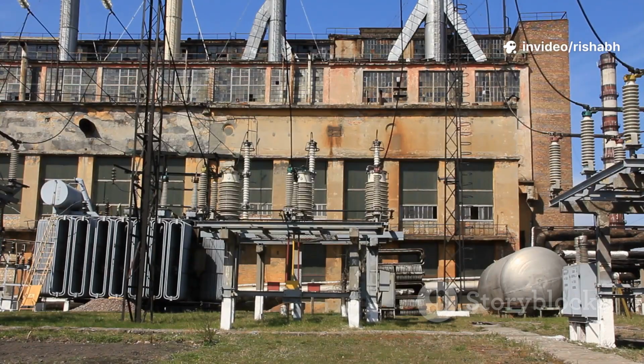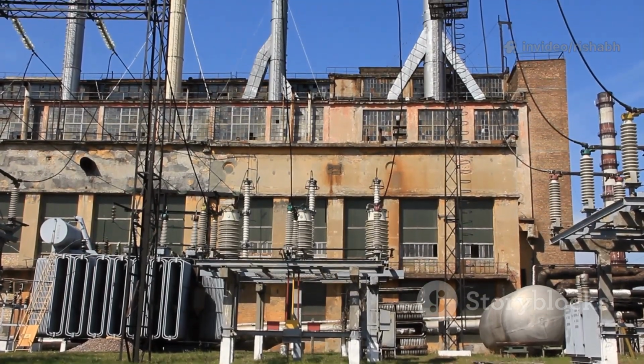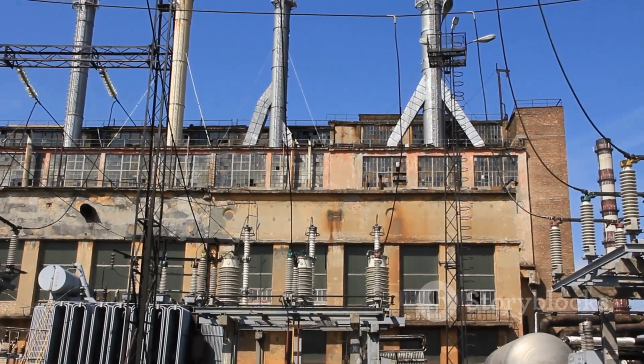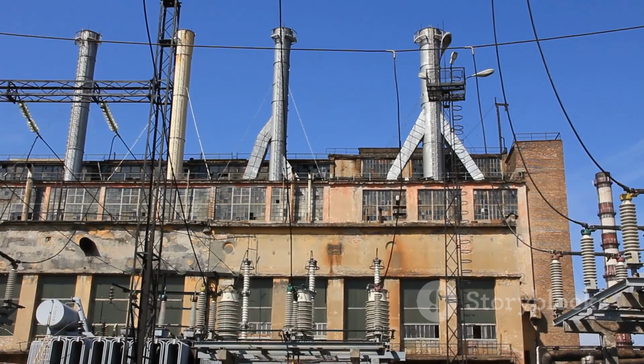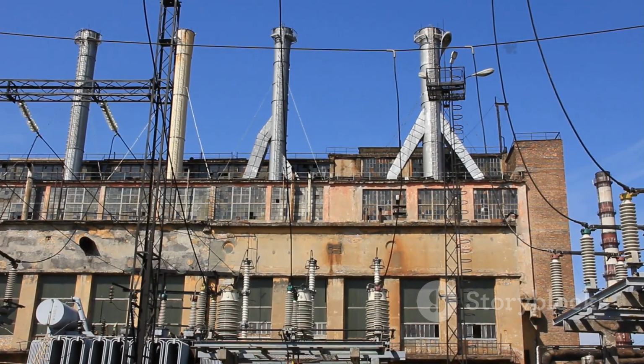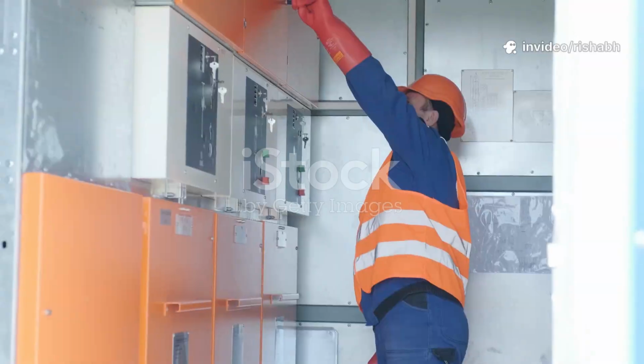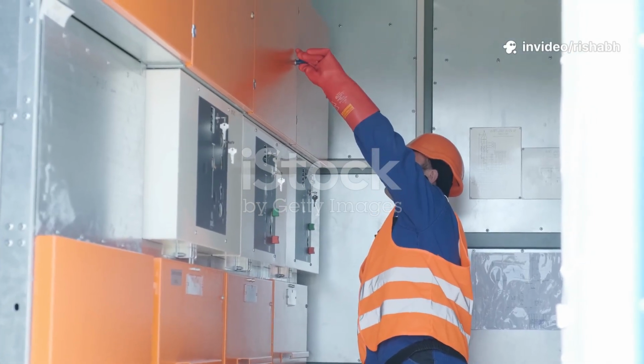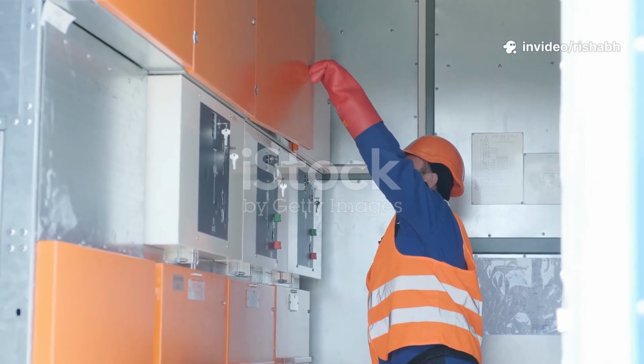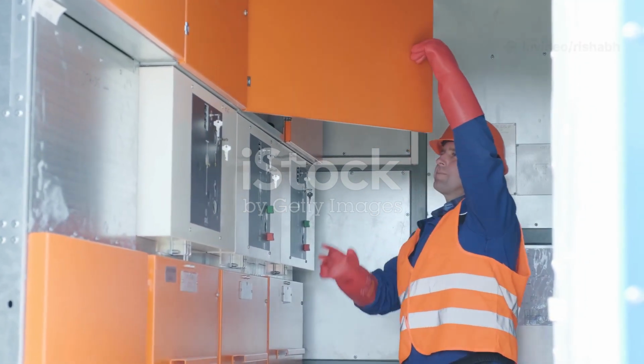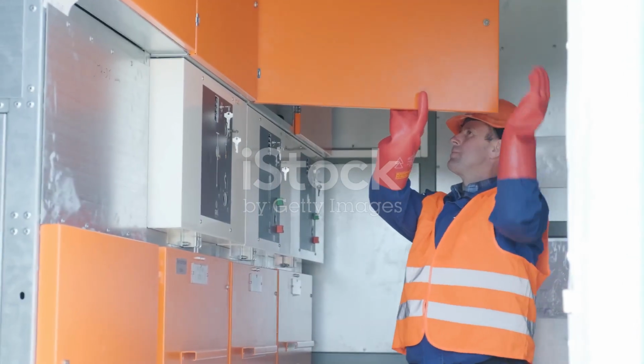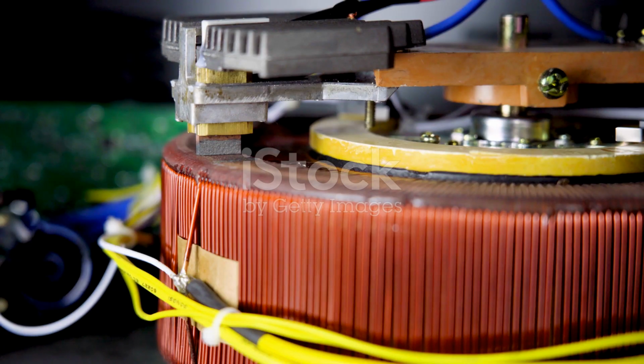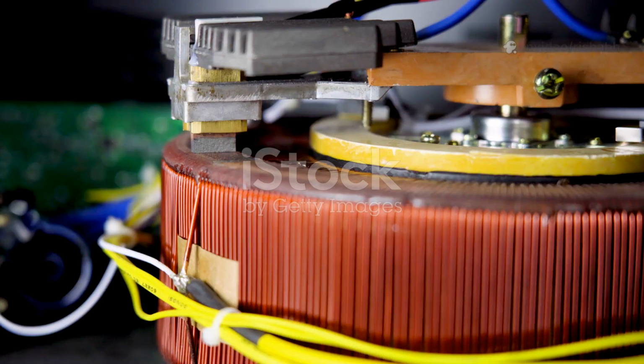Sometimes a third winding, called a tertiary winding, is included. It might be used to supply local power to the substation or to help stabilize voltages in the system. The arrangement of these windings is a matter of careful electrical and mechanical design. The placement of these coils around the core limb is not random. Typically, the low-voltage winding is placed closest to the core.